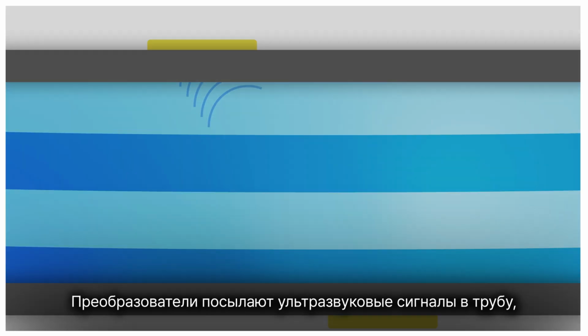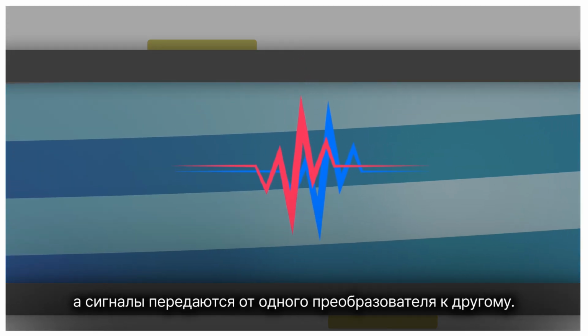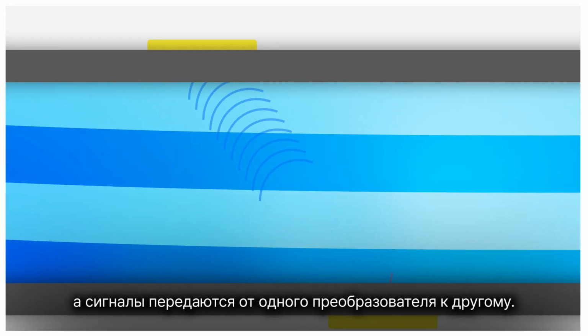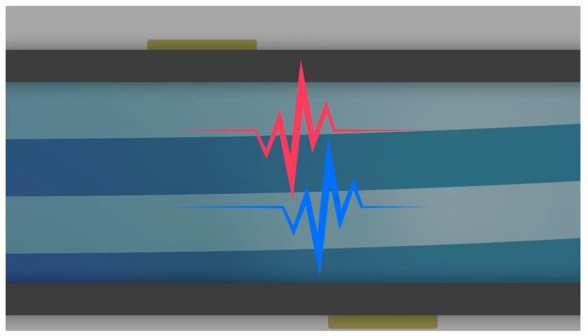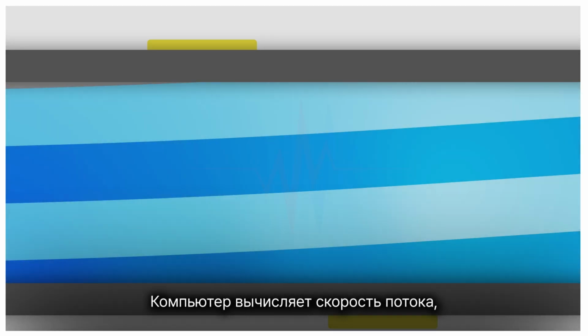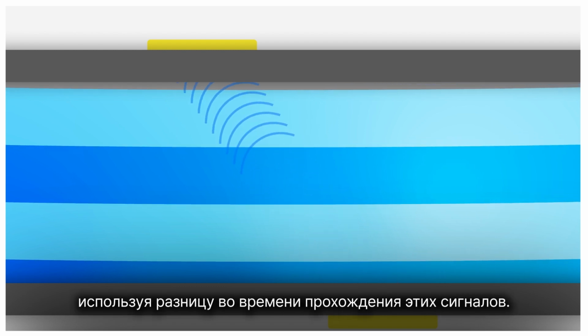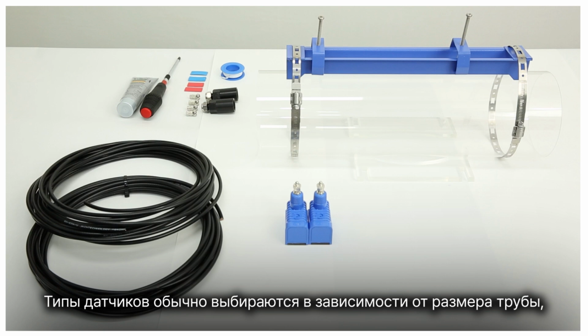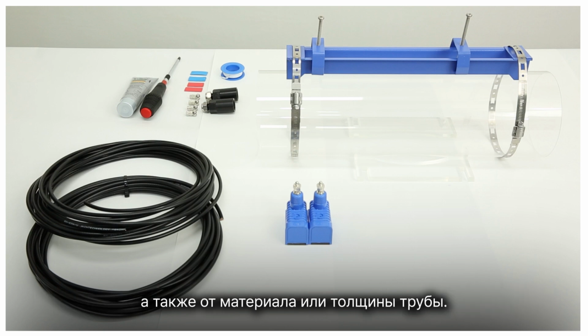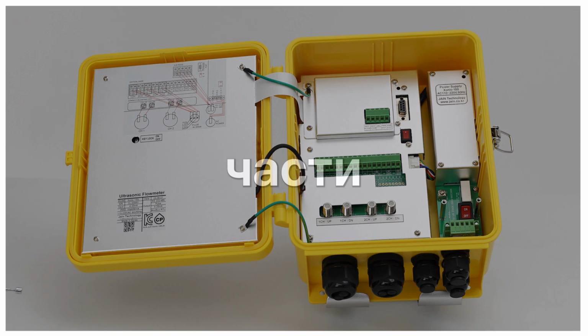Transducers send out ultrasonic signals into the pipe, and the signals are sent back and forth from one transducer to another. The flow computer calculates the flow rate using the transit time differences of those signals. Transducer types are usually selected based on the pipe size, but also on the material or thickness of the pipe. Let's take a look at the parts of the flow computer.